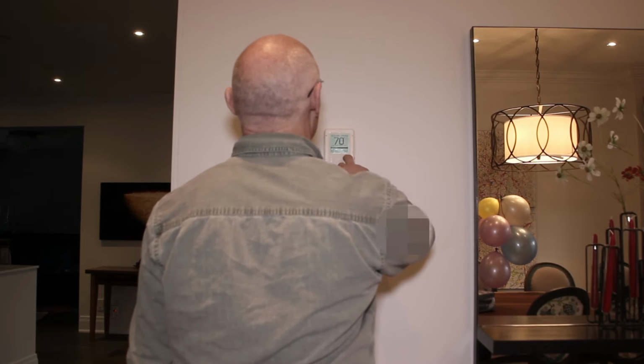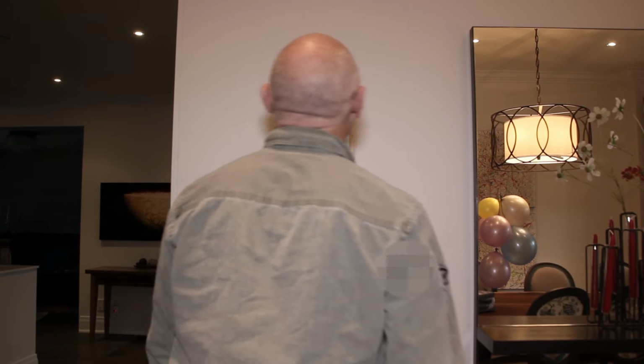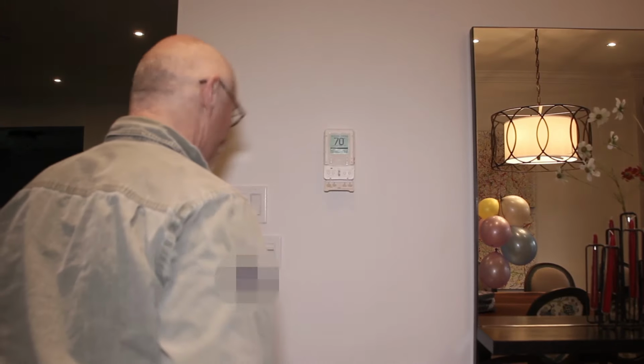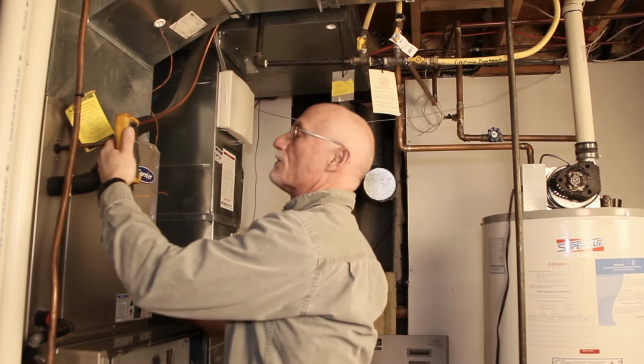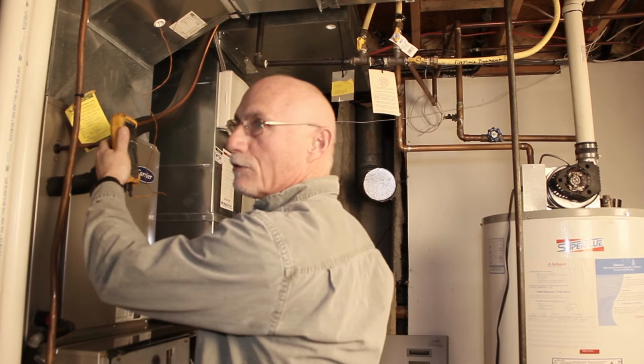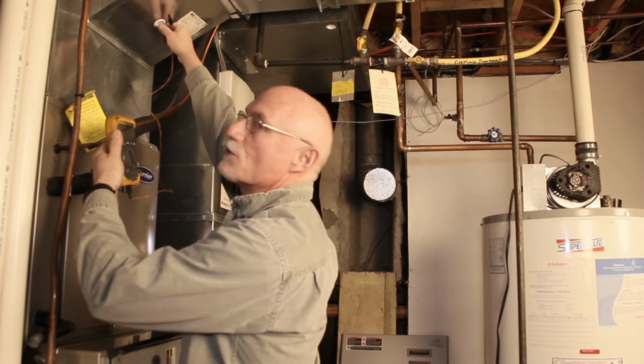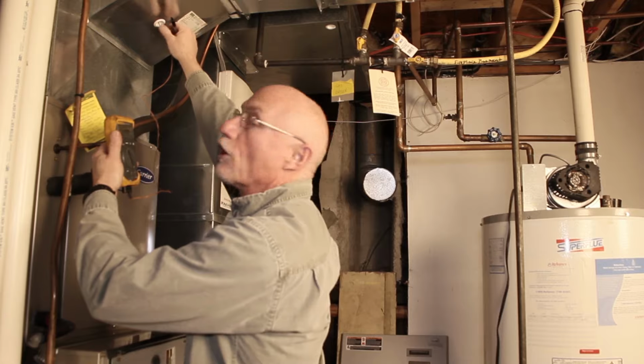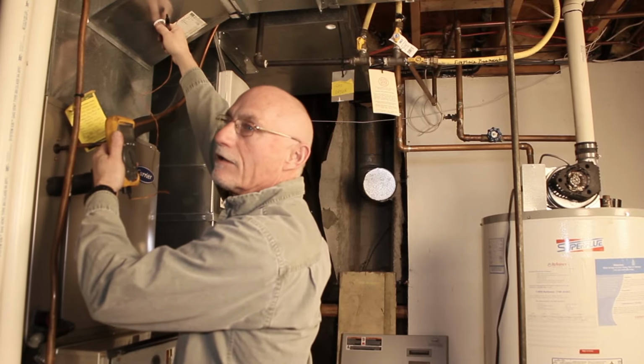So we're just going to turn this up. I've just turned it up for a couple degrees, and if you want to come down, you can watch what I'm doing. And by what it's telling me, the furnace is operating properly within its range. Okay, so this is all good, and I want to go upstairs now and check for carbon monoxide in the home to make sure you have nothing upstairs. Okay?